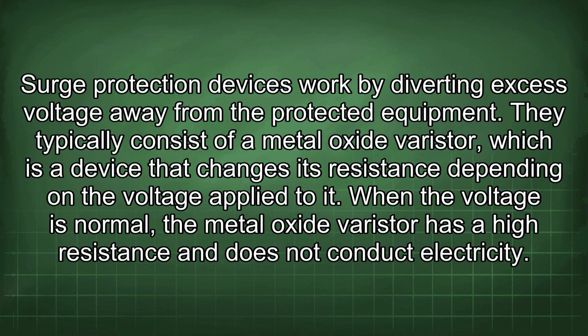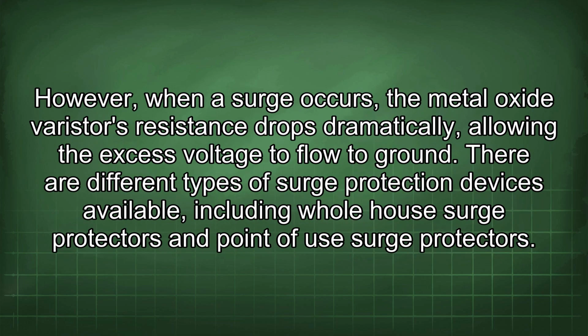They typically consist of a metal oxide varistor, which is a device that changes its resistance depending on the voltage applied to it. When the voltage is normal, the metal oxide varistor has a high resistance and does not conduct electricity. However, when a surge occurs, the metal oxide varistor's resistance drops dramatically, allowing the excess voltage to flow to ground.